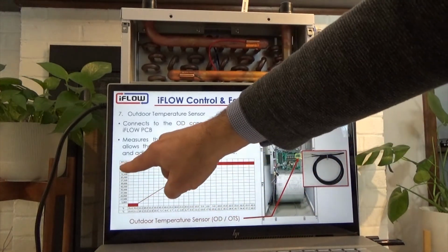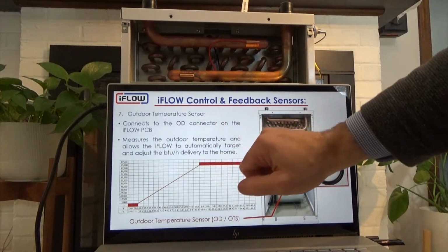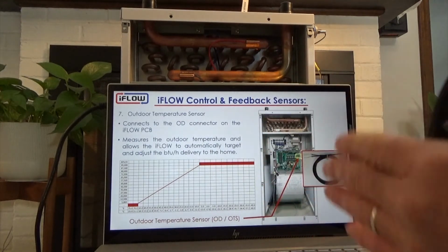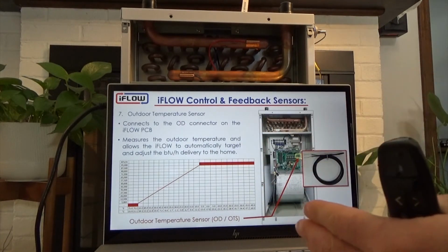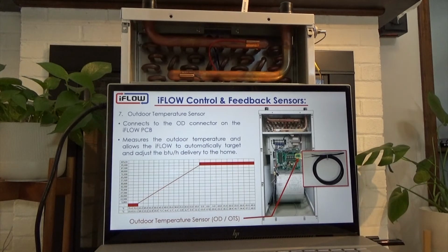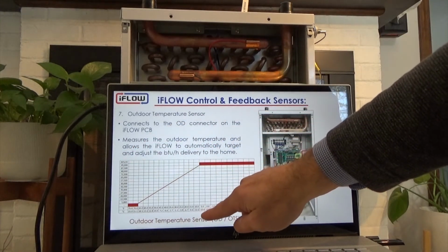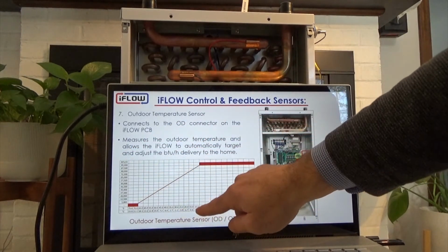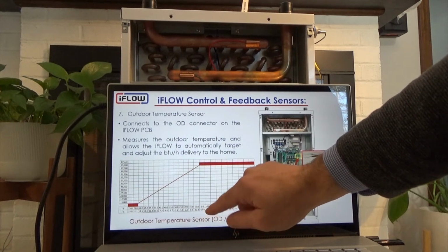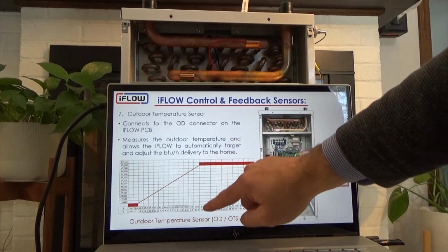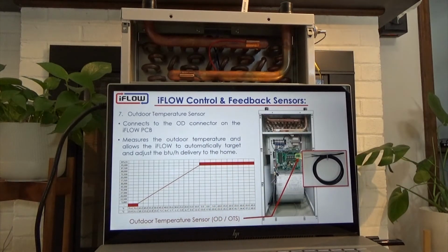So, for example, this is our 18,000 unit. We see we can go as high as 95,000 BTUs. So we decide at what outdoor temperature I need my maximum demand. We look at our heating load plans or our heat load calculations and say, if our design temperature is -15 and that's where we need 95,000 BTUs, then I can set that. So I will set my outdoor temperature where I need maximum BTUs at that temperature, -15 Celsius or 5 degrees Fahrenheit, for example.